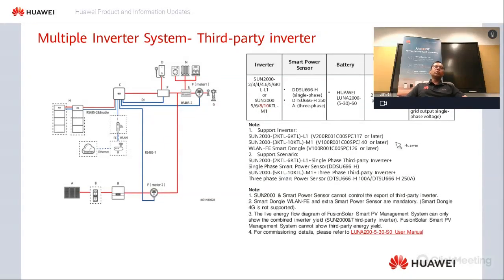This is a quick single line diagram to show that although the Huawei battery is a DC coupled solution, we can use it as a retrofit if the customer has an existing solar system with a third-party inverter connected to PV. We can still add a Huawei Luna battery with a Huawei hybrid inverter. The only additional thing required in this scenario is an additional smart meter at the third-party inverter end, plus the normal smart meter at the switchboard end. These two smart meters communicate and guide the battery regarding charging. If there are any questions about this kind of scenario, please reach out to us, we'll be happy to help.